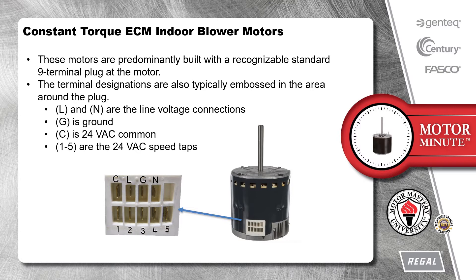Constant Torque ECM Indoor Blower Motors are predominantly built with a recognizable standard 9-terminal plug at the motor. The terminal designations are also typically embossed in the area around the plug. L and N are the line voltage connections, G is ground, C is 24V AC common, and 1 through 5 are the 24V AC speed taps.